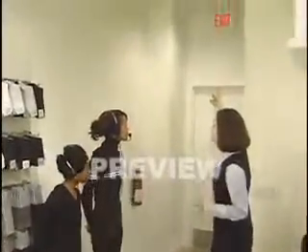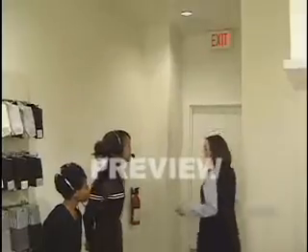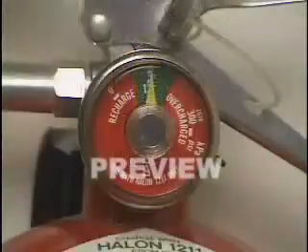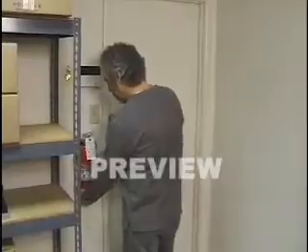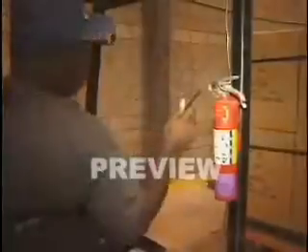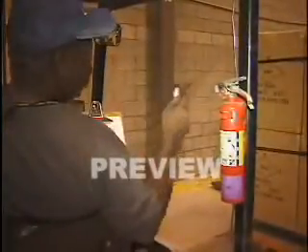Specific evacuation routes, plans, and procedures are posted at your location. If you're not sure where to go or what to do, ask your manager or supervisor to review this critical information. Make it a point to know where the fire extinguishers are located in your facility or office. They must be fully charged, in the green zone, and the inspection tag must be current. Your company has a monthly and yearly inspection plan, but fire extinguishers sometimes just lose pressure, so it doesn't hurt to check them often. Of course, report any problems immediately.